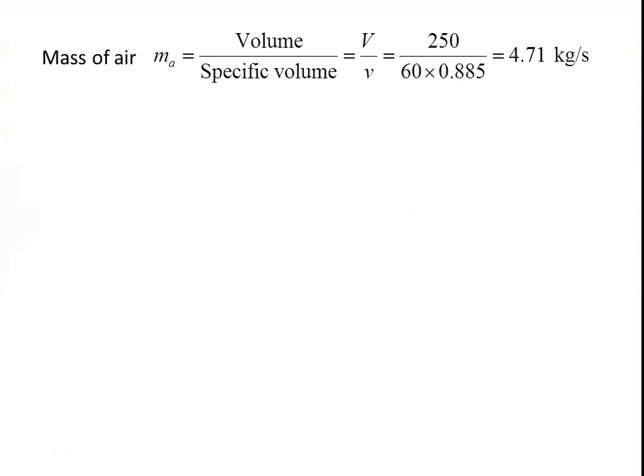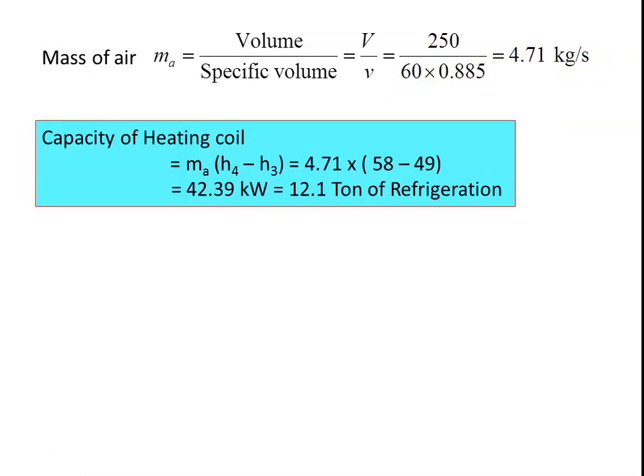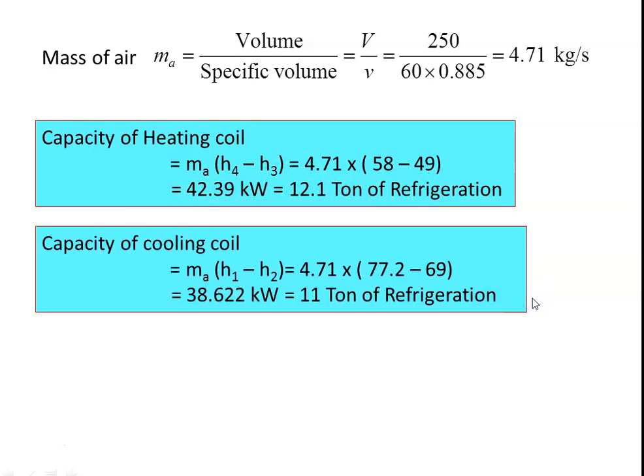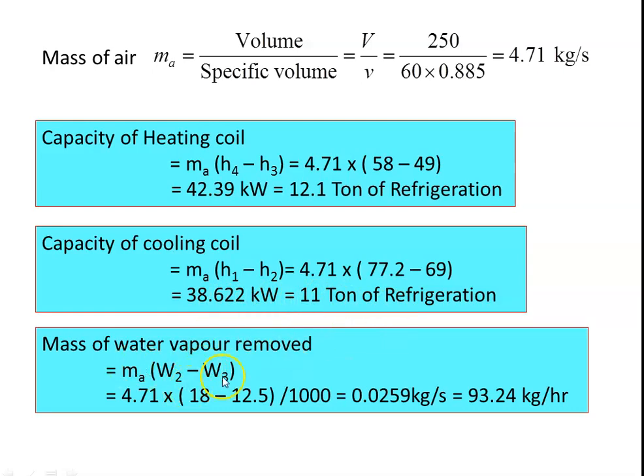Mass of air = 250 / 60 / 0.885 = 4.71 kg/s. Capacity of the heating coil = M × (H4 − H3) = 4.71 × (58 − 49) = 42.39 kW. Capacity of the cooling coil = M × (H1 − H2) = 4.71 × (77.2 − 69) = 38.6 kW. Since 3.5 kW = 1 ton of refrigeration, the cooling coil capacity is 11 tons of refrigeration. Mass of water vapor removed = M × (W2 − W3) = 4.71 × (18 − 12.5) / 1000 = 0.0259 kg/s = 93.24 kg/hour.